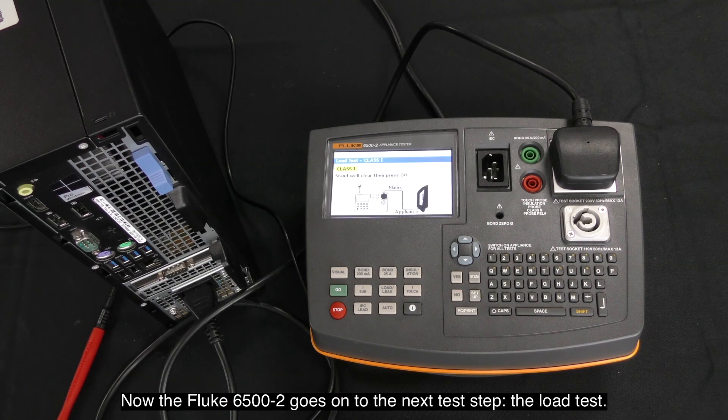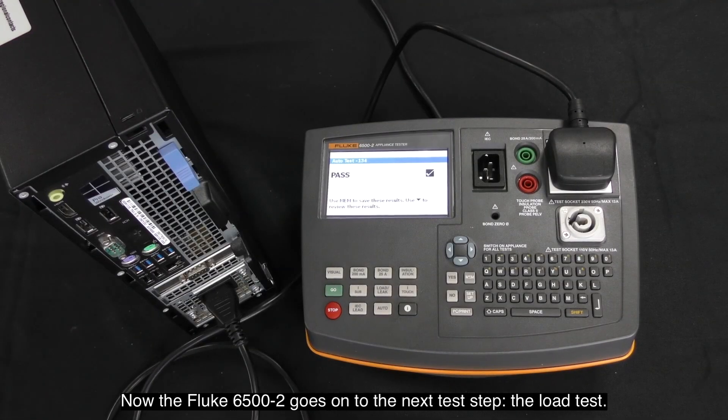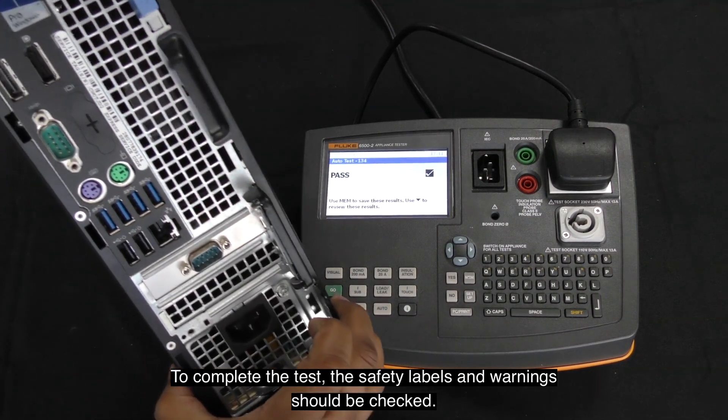The Fluke 6500 Mark II goes on to the next test step, the load test. To complete the test, the safety label and warnings should be checked.